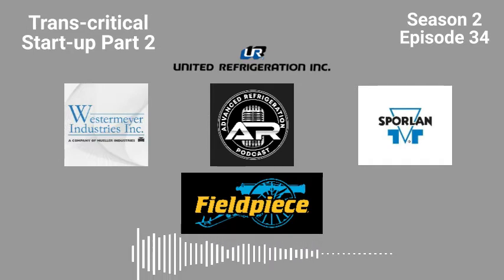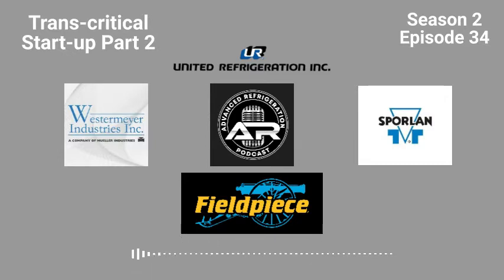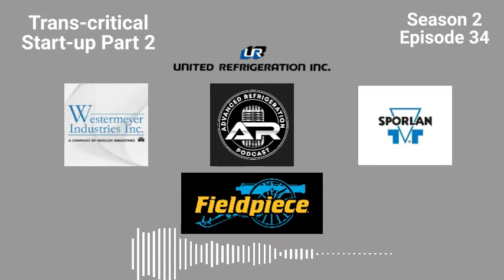The floor in the freezer — all that becomes a nightmare. Staging down the freezer is a complete nightmare because that is the only low temp load. They don't have any low temp — just the freezer. It runs very poorly because you have a digital compressor and usually two more scrolls. It's a decent-sized freezer, but it becomes a nightmare because you have to raise the suction group up. In the beginning, you can pretty much run the freezer off the medium temp and then lower it down, so until you get down to like 20 degrees, you hardly even run the scrolls. The digital cycle is like a machine gun.